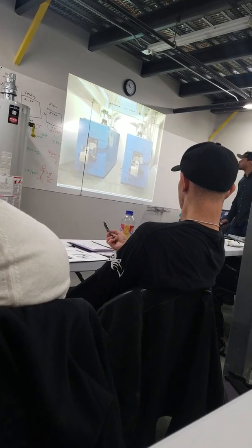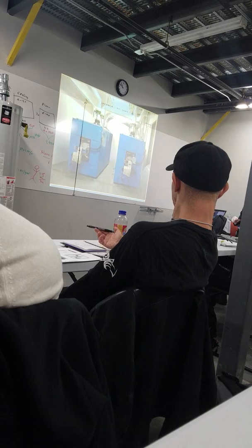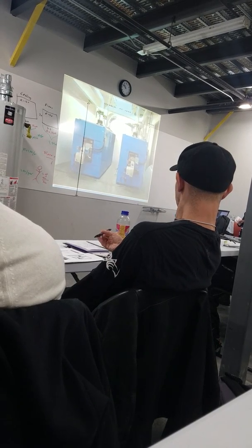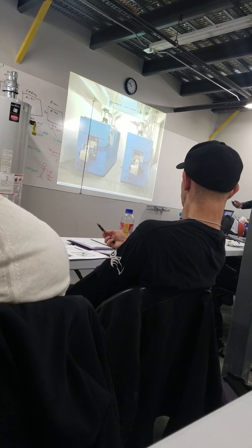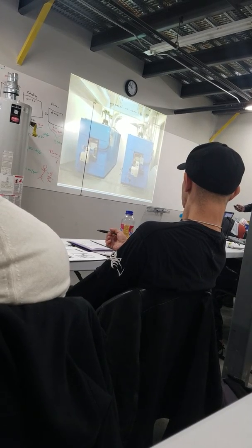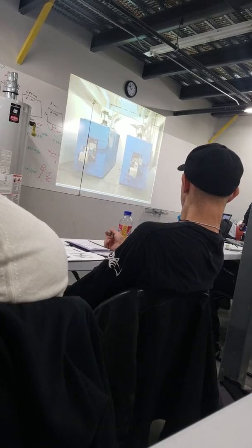Okay, so far we're looking at a cast iron steam system that's oil fired. Good enough. It most likely is atmospherically vented. I can't see it from this angle. It could be sealed, but chances are it's atmospherically vented.